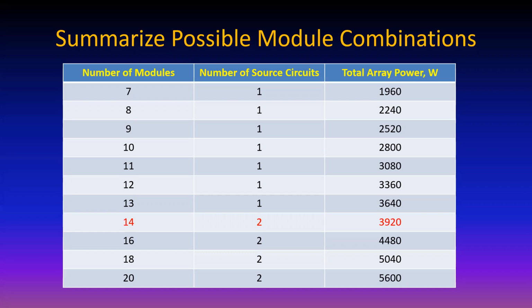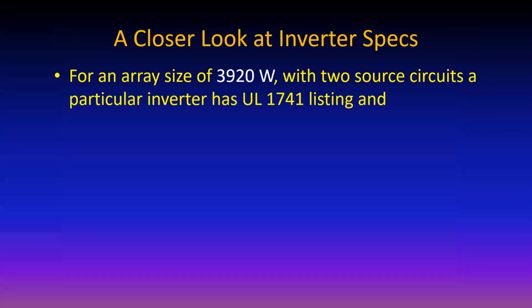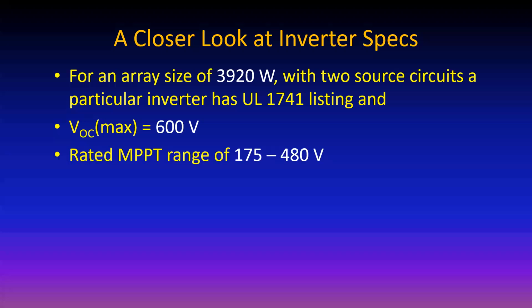All right, so it's an easy table to draw. And the only part we really need is the part for 14 modules. All right, so looking at the inverter specifications, 3,920 watts, 2 source circuits. Your inverter has to be listed to UL 1741. This particular one has maximum input of 600, MPPT range of, let's see, what did we get here?